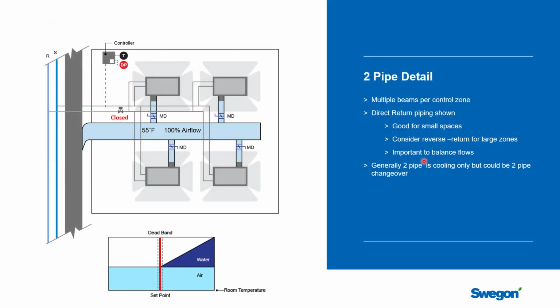Well, let's talk about the piping and the controls in here. We're going to first talk about two-pipe chilled beam applications. So we're going to have a control zone in here. We're going to have 4 beams in this control zone. There's going to be one controller for this control zone that's monitoring the temperature in the space and has some way of keeping an eye on the humidity or the dew point in the space.